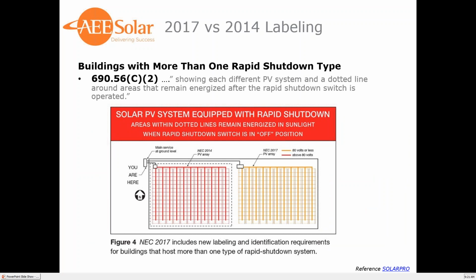For buildings with more than one rapid shutdown type, which will likely be encountered more so in commercial, I would say, but possible in residential, you would need a placard showing the 2 different systems with the 2 different types of rapid shutdown. As you can see on the label, they have part of the array highlighted with a dotted line with red strings going through it, indicating that it's an NEC 2014 PV array, so that it's above 80 volts. And then to the right, it's kind of an orangish yellowish color, saying that it's 80 volts or less in that array boundary.